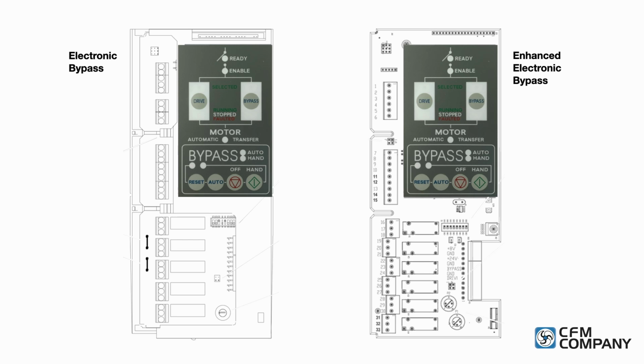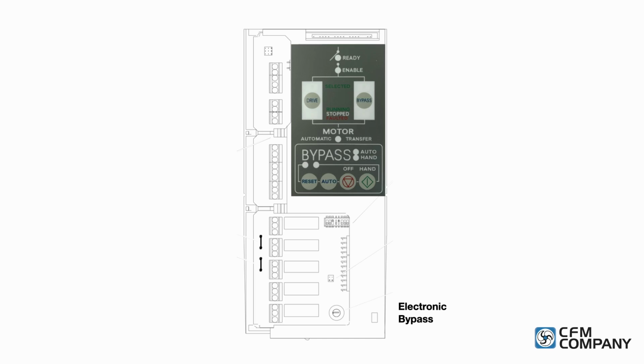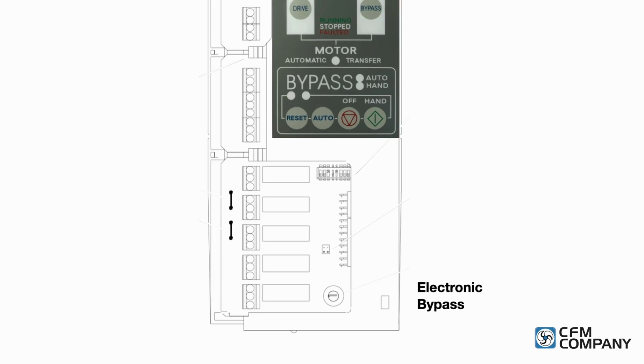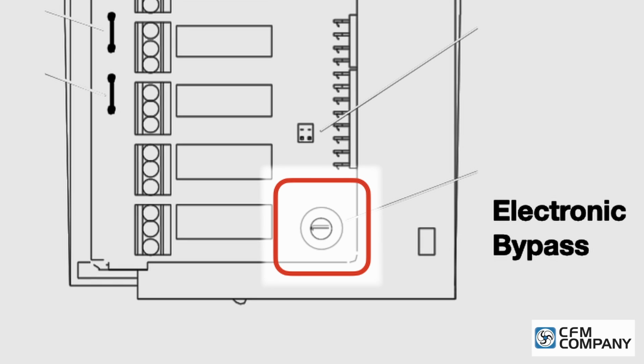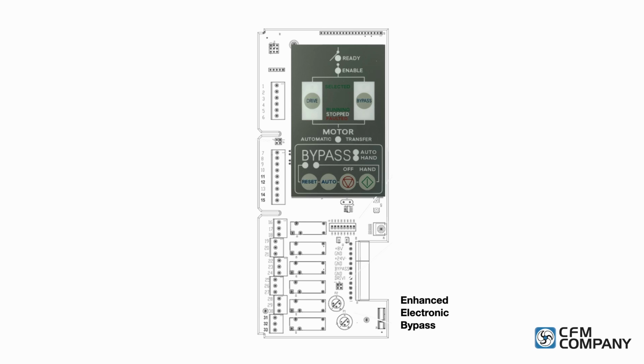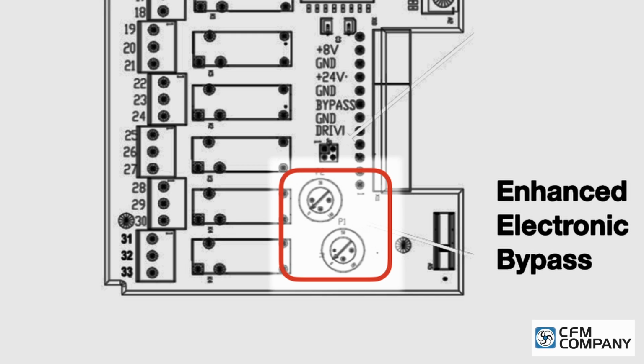There are 2 models of bypass control boards. The original electronic bypass control board is identified with a single adjustable dial in the lower right of the control board. The enhanced electronic bypass control board is identified with dual adjustable dials in the lower right of the control board.